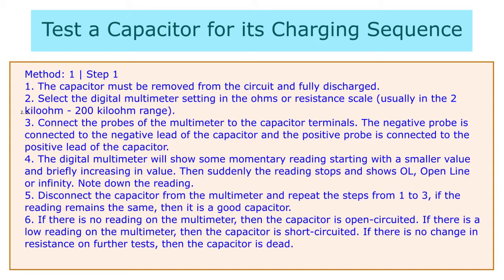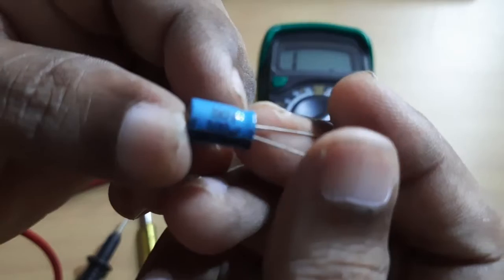This test is done with the following steps as given below. 1. The capacitor must be removed from the circuit and fully discharged. 2. Select the digital multimeter setting in the ohms or resistance scale. 3. Connect the probes of the multimeter to the capacitor terminals. The negative probe is connected to the negative lead of the capacitor and the positive probe is connected to the positive lead of the capacitor.